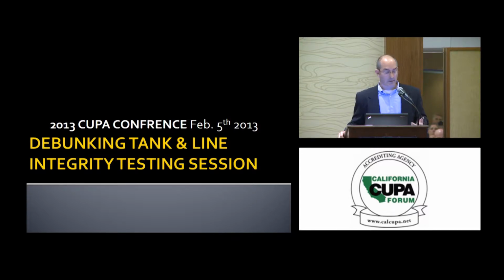There is a feature on our Sure Test to eliminate stiction, or the static friction that may occur on any moving part. If there's not much movement, there could be a little bit of friction. We have a shaker mechanism to help eliminate any of the stiction that may occur. I'm not aware of any ATG probes that use that feature. They do typically have a larger diameter float, which may offset that somewhat.